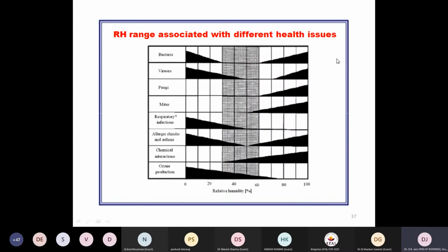This is also a similar chart. Starting toward the middle, the propagation of infectants gets milder and milder. Again, from the middle to the end, the propagation is in a stronger region. So within some fixed humidity range, the propagation will be mild. That gives you the reason for selecting humidity maintenance with a desiccant-based cooling system that can control the humidity in an effective way.